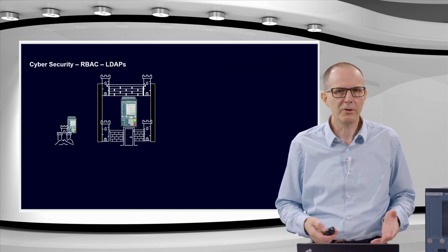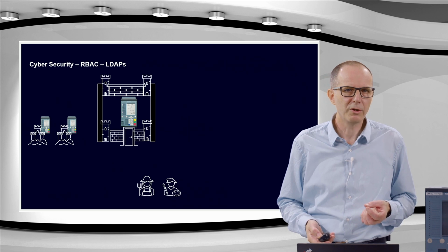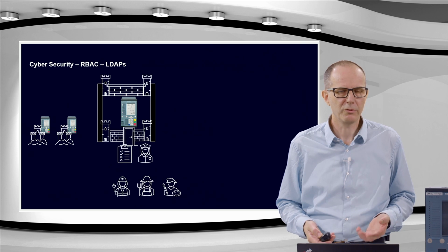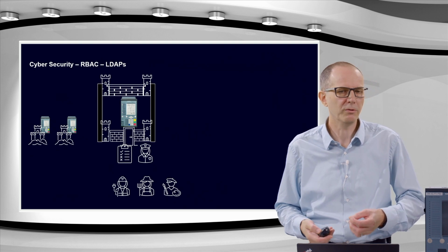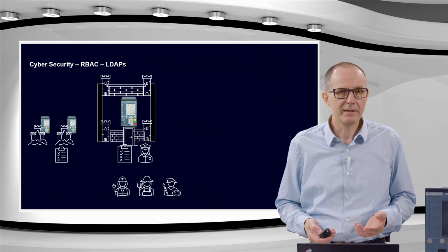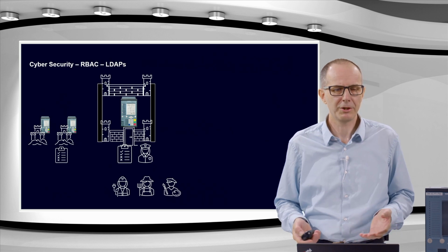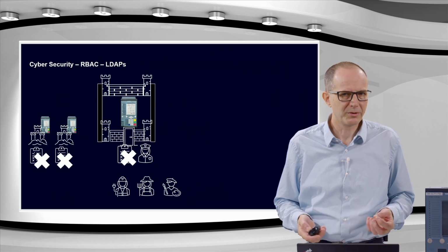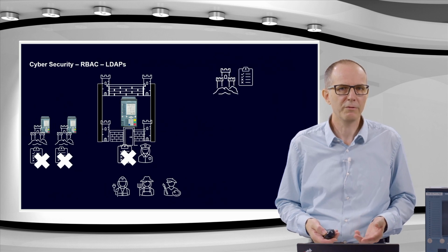And in a substation you have a lot of them. Now we have the people who want to work with it, depending on the role they have. So to protect the access, your guardian needs a list of the people and the credential or the password of the people. This access list is also needed for all the devices and must be maintained, because passwords change, user roles change, users change. So that is not a practical solution. The solution is a central management of the user access.